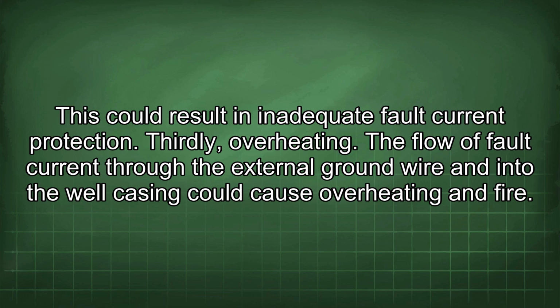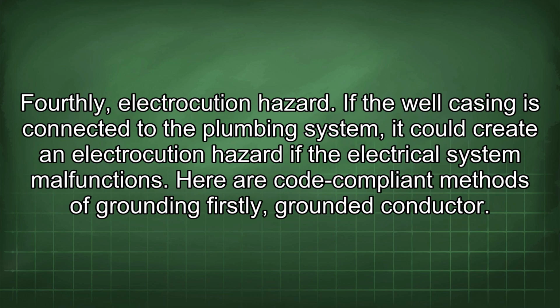Thirdly, overheating. The flow of fault current through the external ground wire and into the well casing could cause overheating and fire. Fourthly, electrocution hazard. If the well casing is connected to the plumbing system, it could create an electrocution hazard if the electrical system malfunctions. Here are code-compliant methods of grounding.